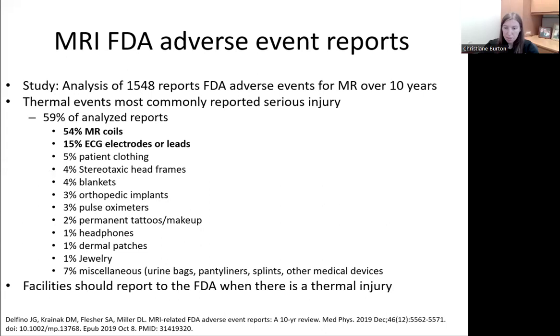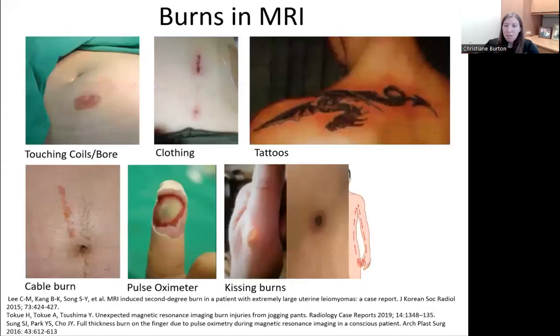I'm going to illustrate these types of thermal injuries in the next few slides, so I do need to warn you that the pictures you are about to see are not pretty. These types of thermal injuries do happen in MRI machines everywhere, internationally, nationally. The patient's touching the bore and/or coils. There is a specialized MR foam padding that should be used, not sheets or towels, to prevent patients from touching the walls of the scanner or the local coils. This may be difficult in very large patients, but it must be done.